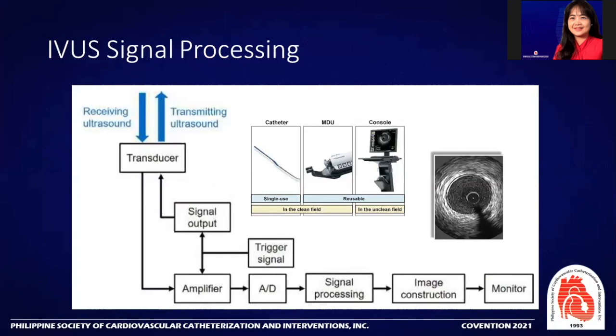Now here are the three components of the device system of Ivus: the catheter, where the transducer is, the motor drive unit, or MDU. This rotates the transducer and does automatic pullback. And of course, the console. This is where we assess and measure the image through the monitor.